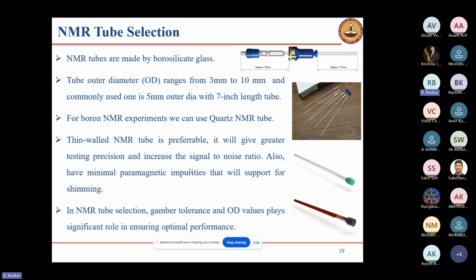These NMR tubes are made of normal borosilicate glass. For regular experiments, we can use this borosilicate glass NMR tube. For boron NMR, we have to use a quartz NMR tube, or Teflon NMR tubes are also available. Always choose a thin-walled NMR tube, because a thicker tube has boron and other quadrupolar nuclei, which will affect the shimming. Finally, we will get bad shimming and not a high-quality NMR spectrum. Camber tolerance means how straight and perfect the tube is. If it is not perfect, it will affect the shimming, so always choose a higher camber tolerance NMR tube.